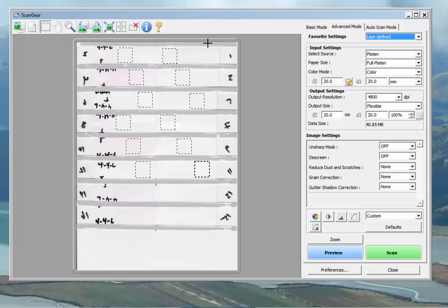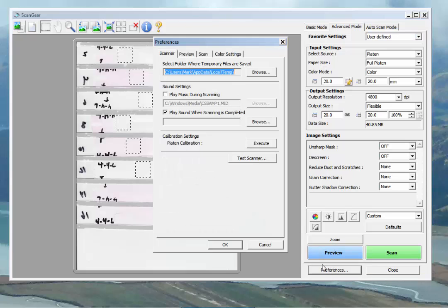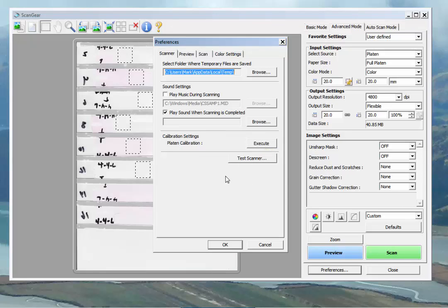So we can load six more, in this case six more folded cards, or twelve individual cards, and run the next batch. All of our settings have stayed identical. And so we're good to go. If for some reason you've turned the scanner off or left it for a week, or any amount of time, more than a couple of days, you probably should go through the preferences routine and run calibration one more time. It only takes a second, and it's a good practice.